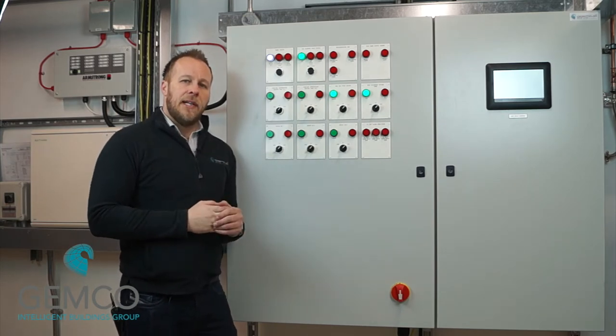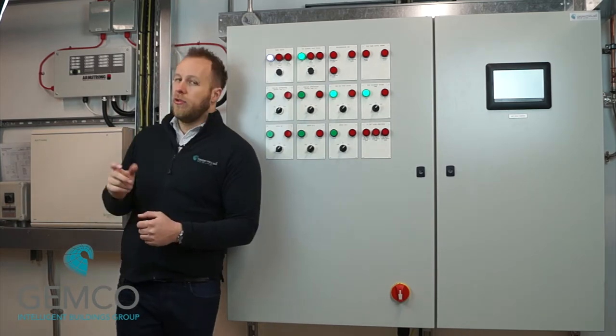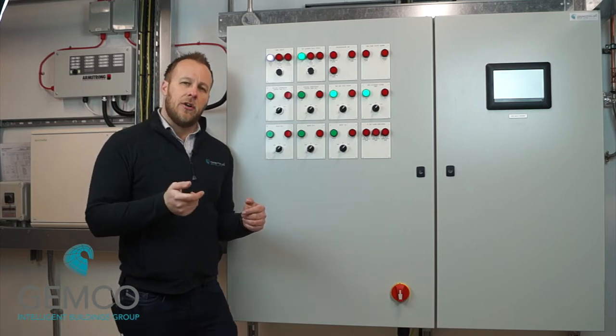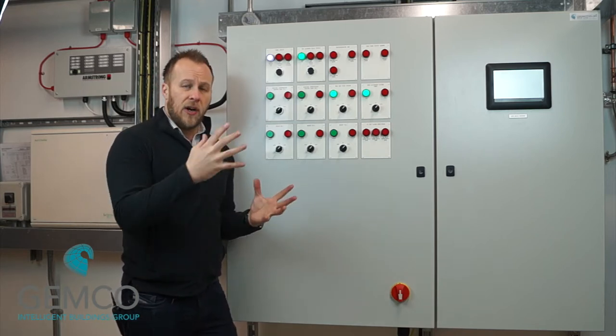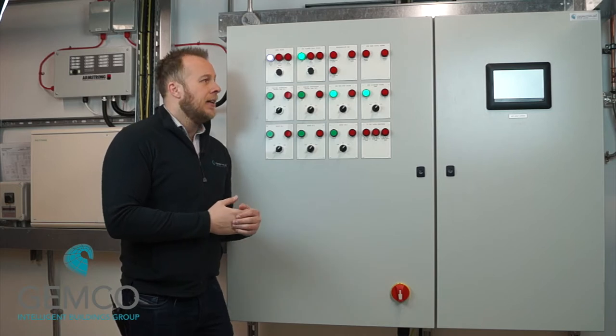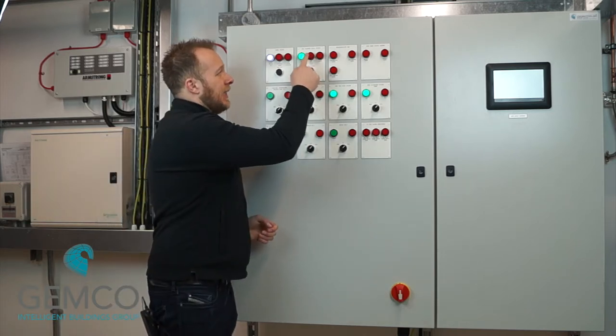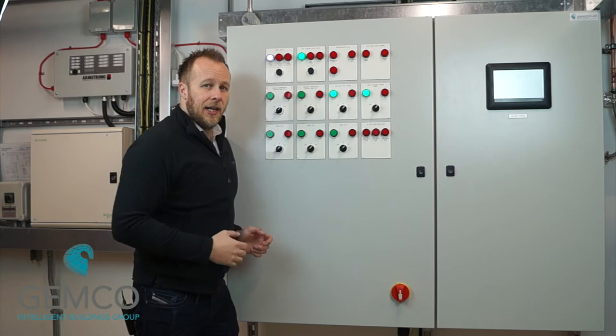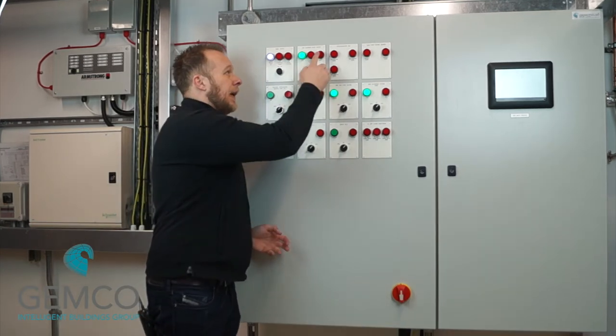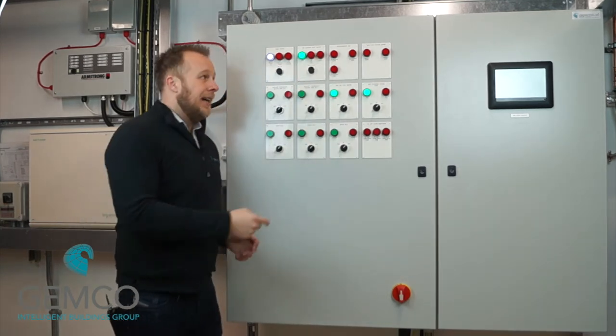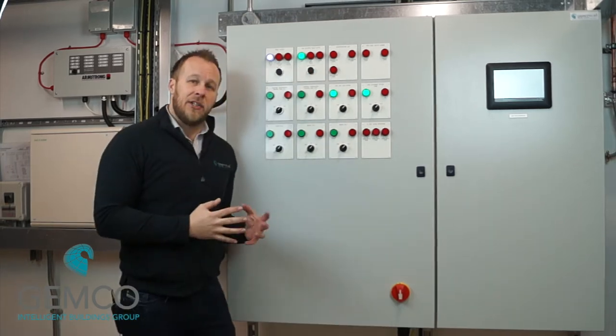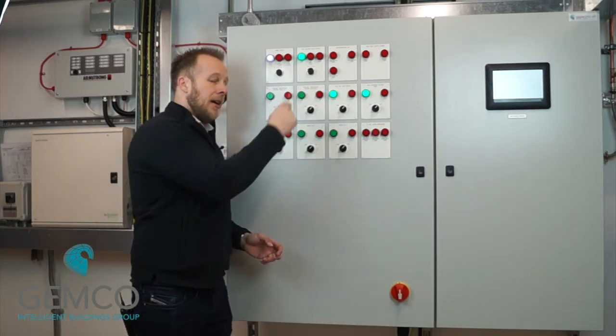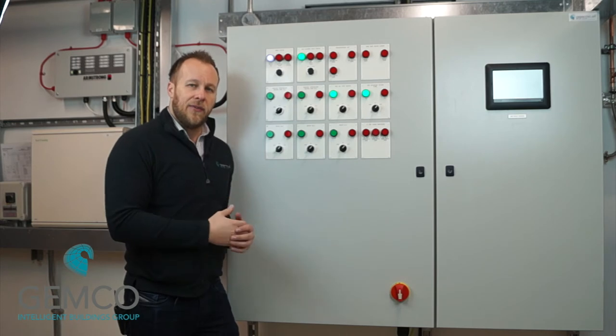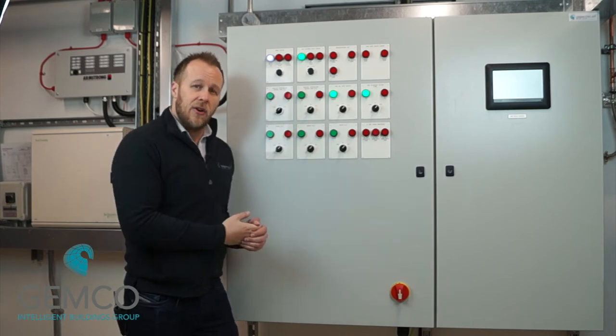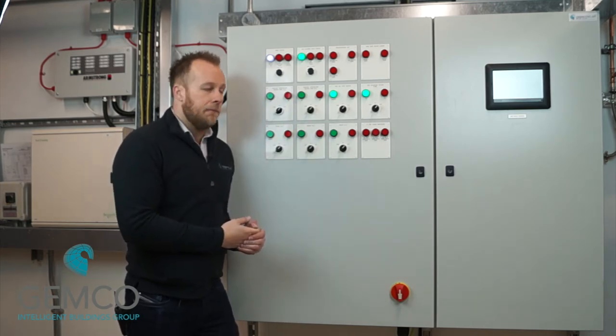Now what will happen is, once you rectify the problem, so if you reset the knockoff button, or the fire system's healthy again, this gas safety circuit failed light will go out to let you know that the problem's been rectified, but the closed light will stay lit until you've pressed the reset. So you say, I'm happy to press the reset, I'm going to reset the gas valve. And then as long as all of those safety circuits are healthy, the gas valve will come back on.